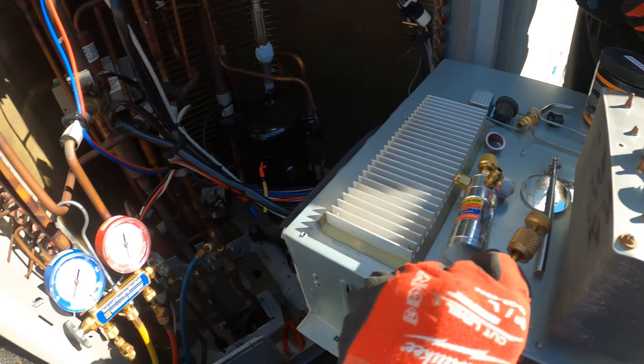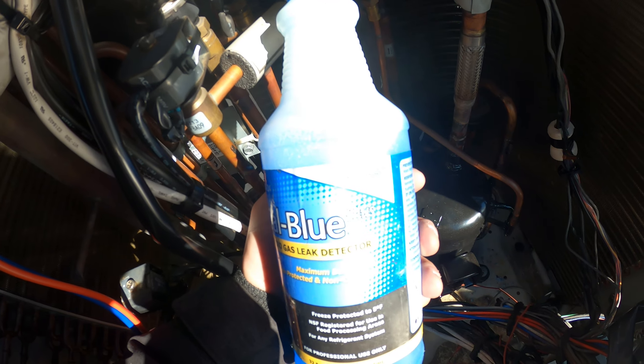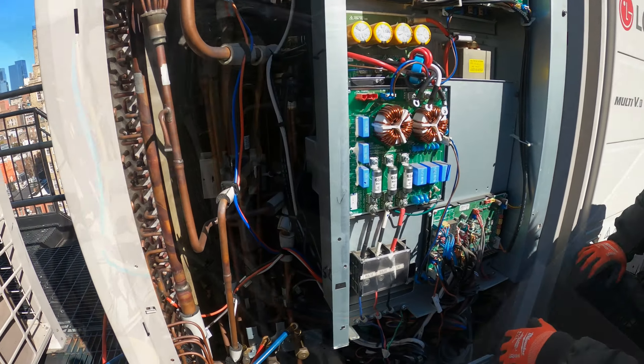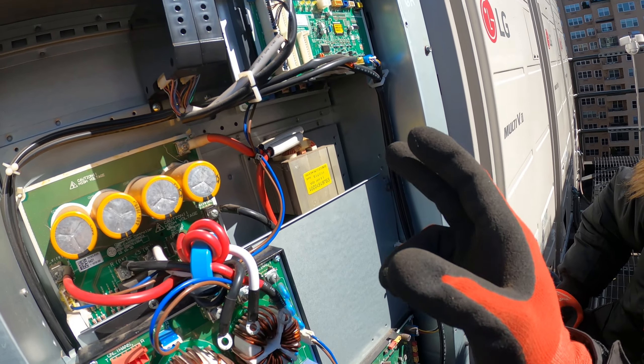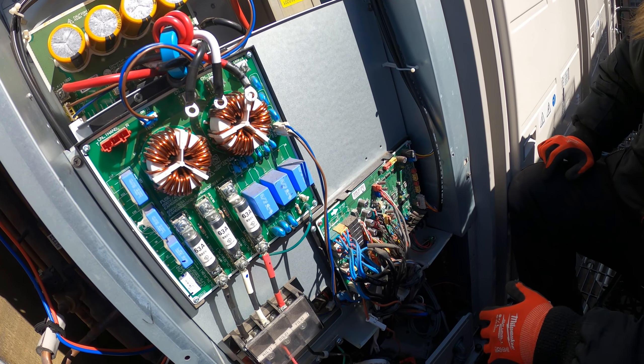Make sure we got no leaks — but then again a vacuum would also tell us we have a leak or not. Let's change these that we took off and get that back on. Let's pressurize and see if we can find anything — alright, micro leak detector, wet everything. Everything's looking pretty good. We threw this panel back on, dumped the nitro.